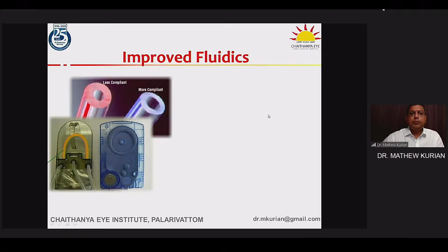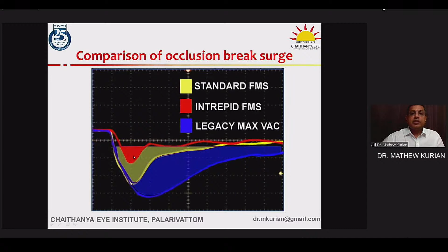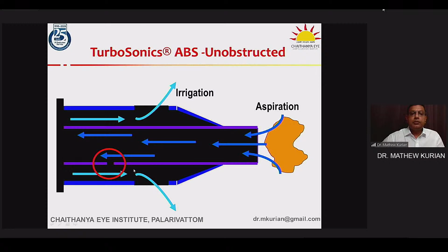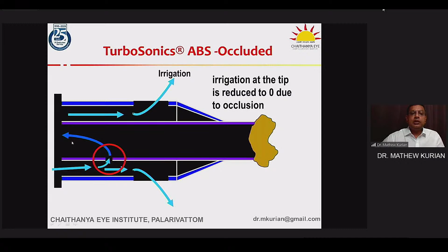So improved fluidics happens with the less compliant tubing, which is harder and less likely to collapse. In the older tubings associated with the legacy, the amount of vacuum drop in IOP after vacuum occlusion was higher and recovery was much slower. In the more modern machines, you will find in the Infiniti, for example, that the dip is much less and the recovery is much faster. The Turbosonics ABS tip has a small hole in the side of the phaco tip. So when there is free flow of fluid from the anterior chamber, there is no problem. This is not required. But when occlusion happens, some of the irrigation fluid is able to negate the vacuum buildup that happens in the aspiration line.